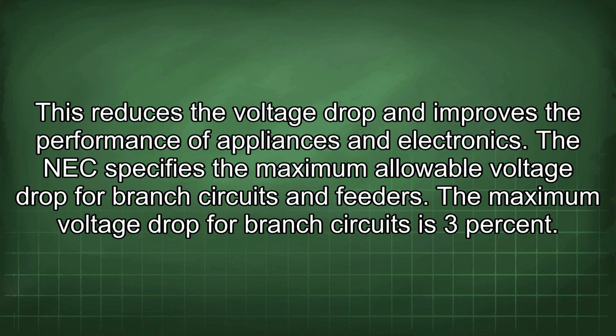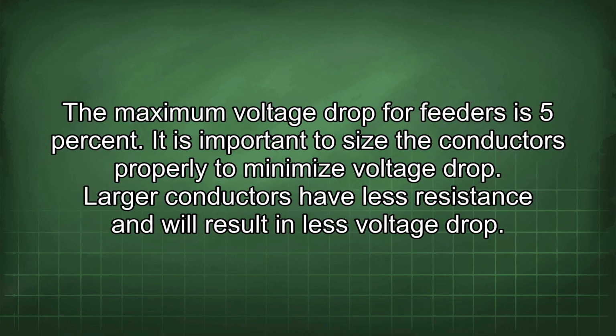The NEC specifies the maximum allowable voltage drop for branch circuits and feeders. The maximum voltage drop for branch circuits is 3%. The maximum voltage drop for feeders is 5%. It is important to size the conductors properly to minimize voltage drop. Larger conductors have less resistance and will result in less voltage drop.